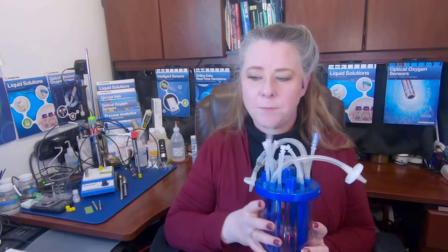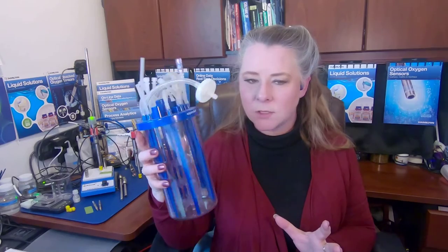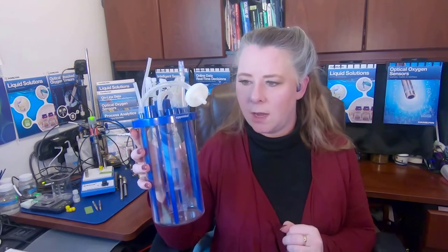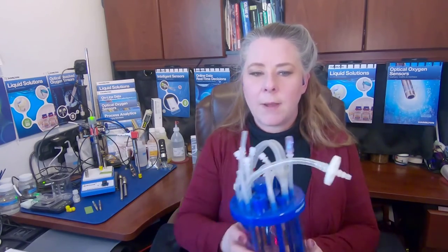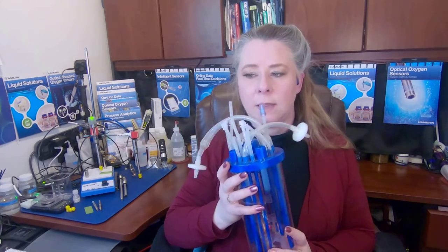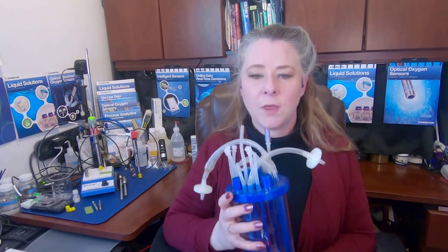Okay. In small tabletop bioreactors like this, you don't generally do an online measurement. For that, we're talking about the really large ones that have huge tanks, 1500 liter, 10,000 liter, 50,000 liter. They might have a little oxygen sensor on the side of the tank that's actually monitoring the headspace. And then there's inline measurements. The cool thing about inline measurements is they are real time and they are consistent.